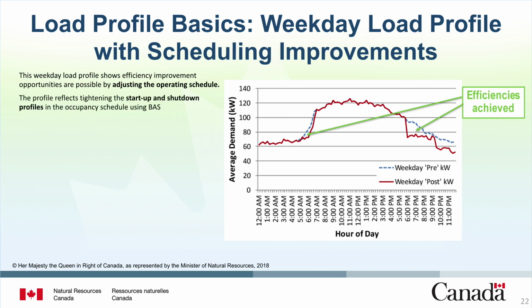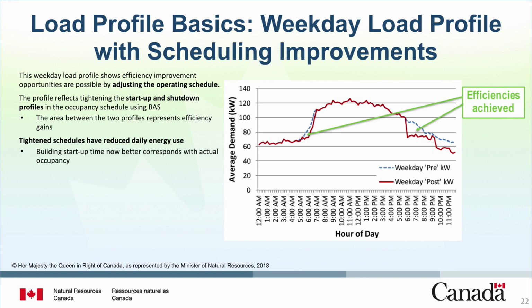This profile reflects actions implemented to tighten the startup and shutdown profiles in the occupancy schedule using the Building Automation System, or BAS. Ramp-up start time was moved from 5:30 to 7 a.m., and the shutdown was initiated at 6 p.m. The area between the two profiles reflects achieved efficiency gains. While the electricity load magnitudes have not changed, the tightened schedules have reduced daily energy use. Building startup time now better corresponds with actual occupancy.